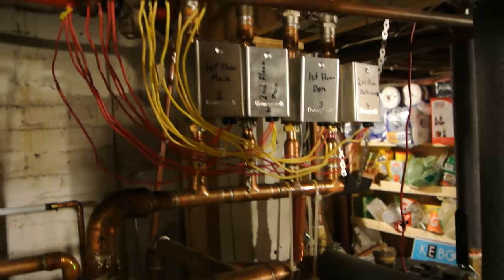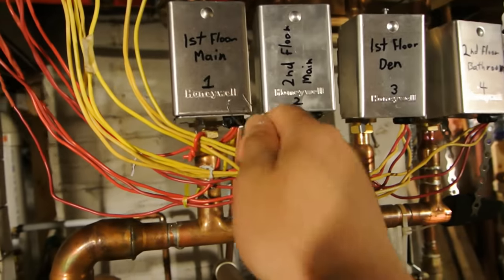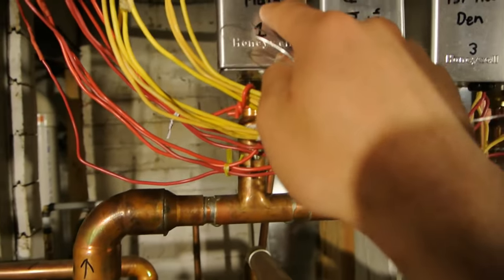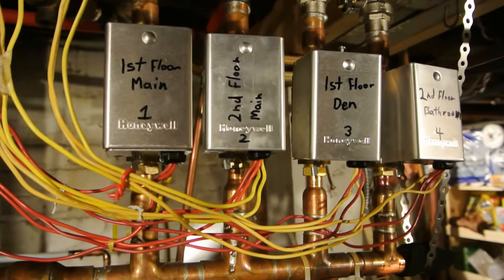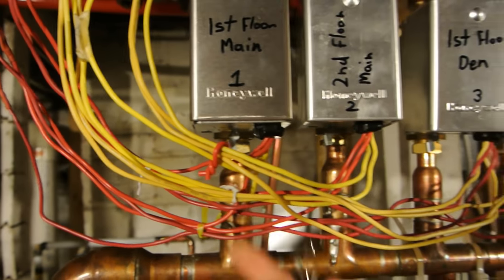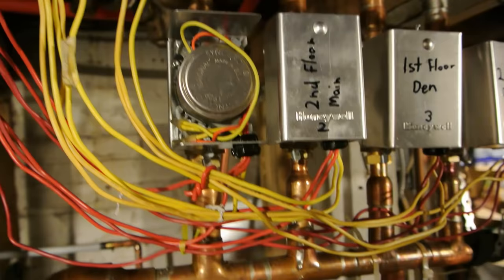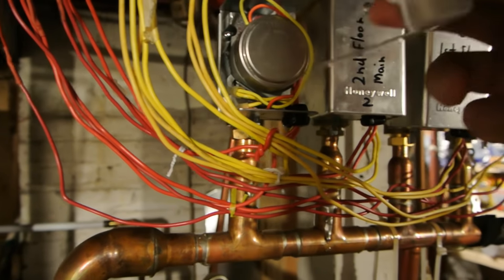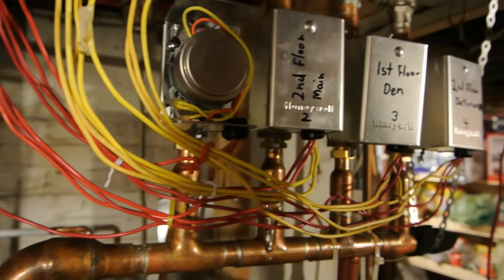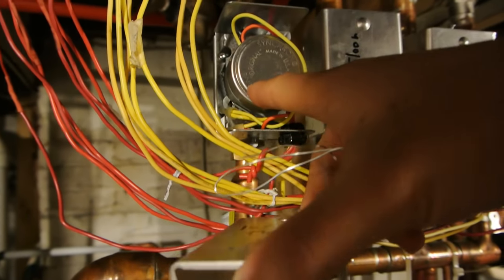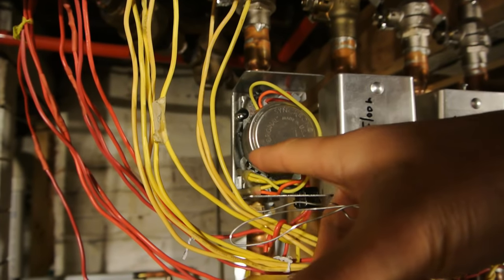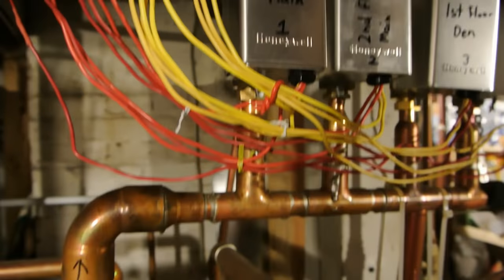These are the zone valves. This one is for the heating loop — there are four zones labeled: main, second floor, den, and bathroom. When you call for heat from the thermostat in any one of the zones, this switch will move over. Inside there's a motor, so this is an electromechanical valve. The motor turns on and opens the valve, letting hot water go through the system. At the end there's an end switch — a little micro switch — and an arm hits it, telling the boiler to turn on.